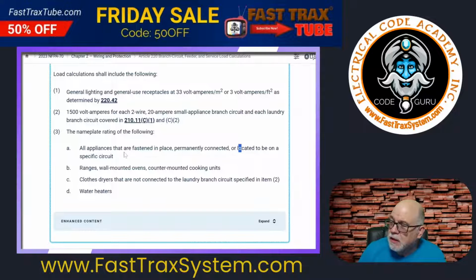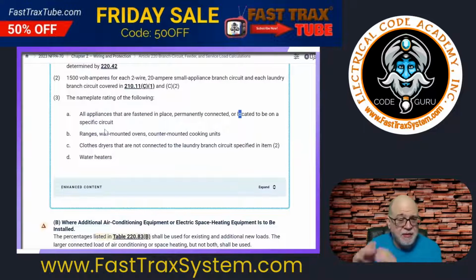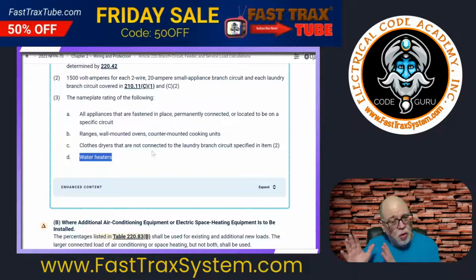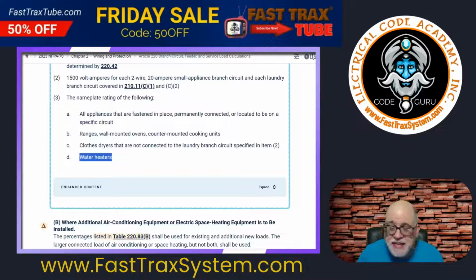Now you're also going around and just taking nameplates, is what it says here. Ranges, same way. Go pick up your load for your ranges. They all have nameplates on them. Your wall-mounted ovens or counter-mounted cooking units. You're just going to be a nice little sleuth and go around and gather all that info. Clothes dryer, the same. Again, we're not talking about the laundry circuit. That was covered up in item number 2 right here. So we're not talking about that. So specific circuit, 30 amp circuit for your dryer, that type of thing. And then, of course, any of the water heaters that you have.